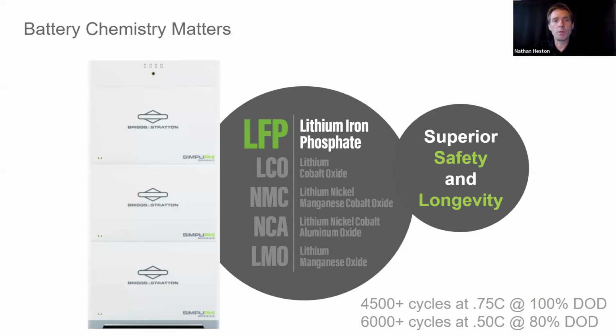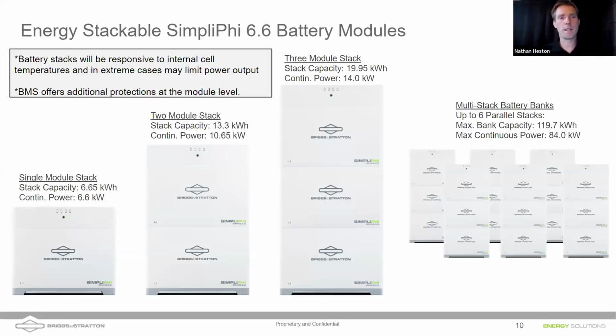We're sticking with the LFP battery chemistry, but we've enhanced the electrolyte a little bit in this newest battery, allowing lower temperature operation. This battery can discharge when ambient temperature is from -4 Fahrenheit all the way up to about 135 Fahrenheit, and it can charge from 14 Fahrenheit up to about 128. I don't know the exact transition point, but I'll show you those numbers on screen in a bit. So there's a wide temperature range we can operate in with this battery.